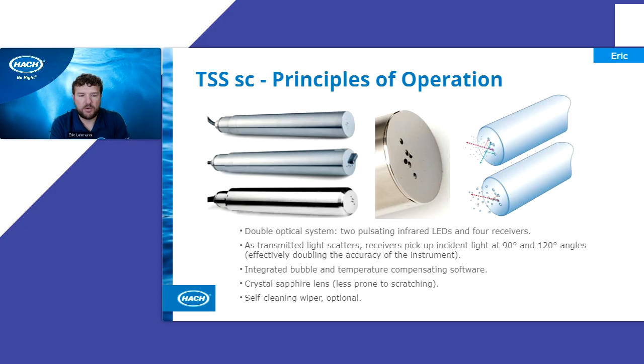Some things to point out: it has integrated bubble and temperature compensation software, so to a degree, it will compensate for bubbles. However, of course, we wouldn't want to install it in, say, an aeration basin above a diffuser or some sort of blowers, so keep that in mind. Another thing is that it is color independent. If there's color in the sample, that will not affect the readings of the probes themselves.